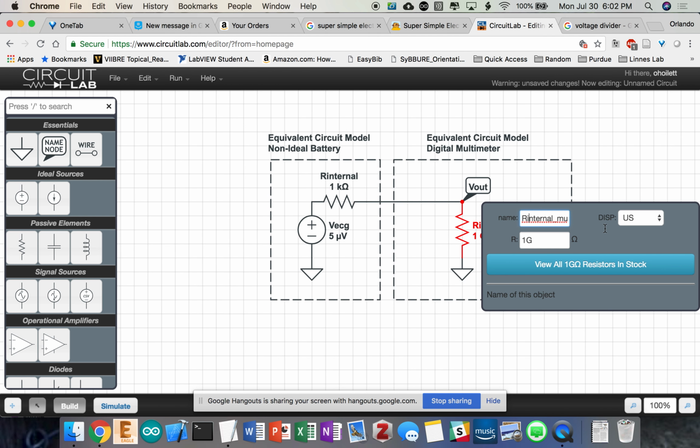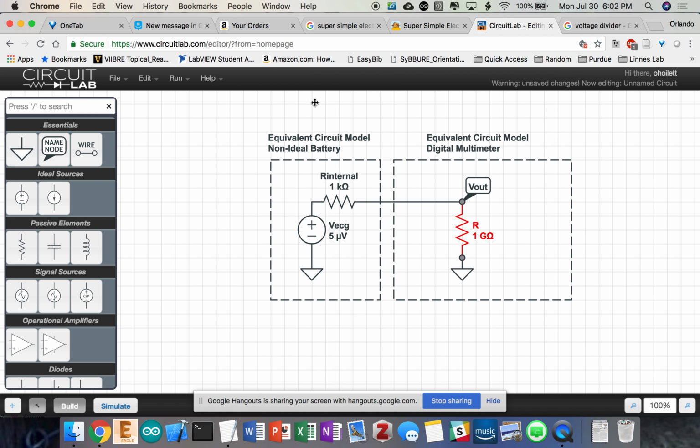Honestly, that is the best way to put it. People always say the higher the better, because in some measurement systems, like for electrocardiogram or things like that, you can have internal resistances, honestly, even all the way up to mega ohms, depending on your electrodes and all those types of things. And I'll actually go into and explain that a little bit more as well. So you want this to be incredibly high.